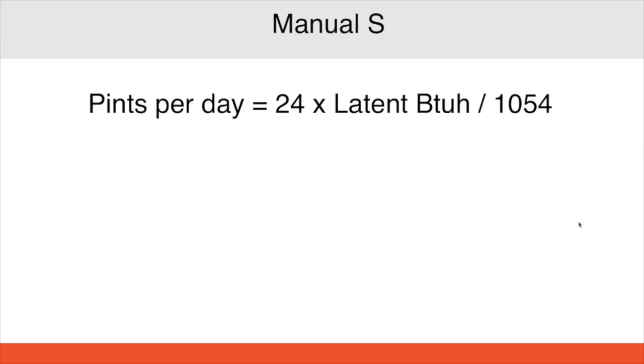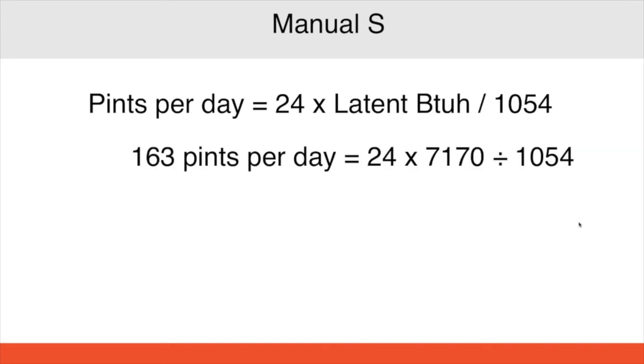So if we look at Manual S, on page 49 of Manual S, it discusses for several pages actually how to size dehumidifiers. And a lot of people don't even realize that is in Manual S, but it is. And we currently are working with ACCA on providing updates to Manual S for their dehumidification section. So pints per day equals 24 hours in a day times the latent BTU divided by 1,054. So again, it's kind of just working it backwards. And again, we still end up with that 163 pints per day.